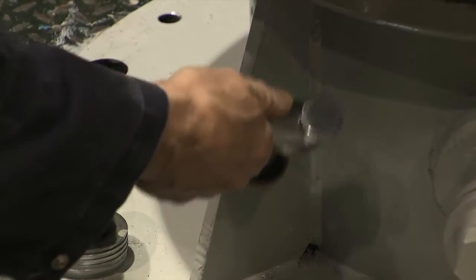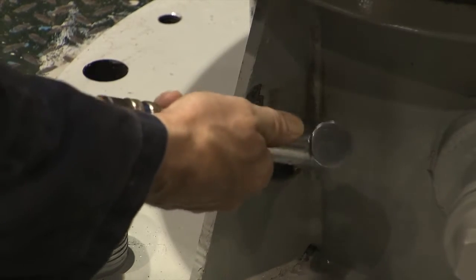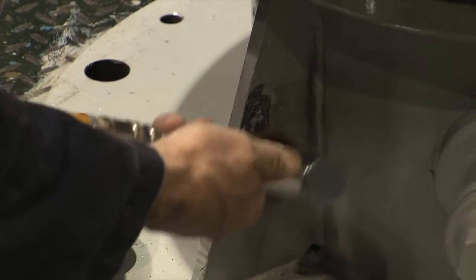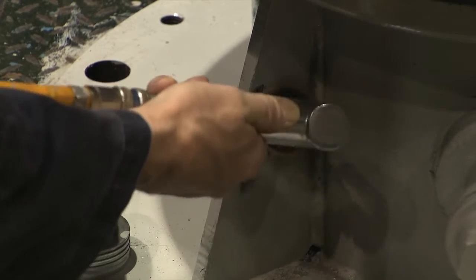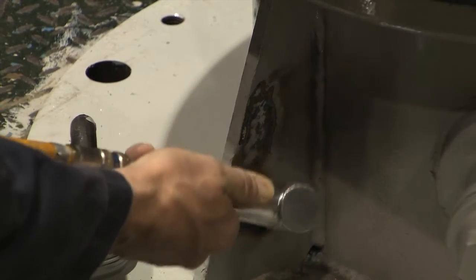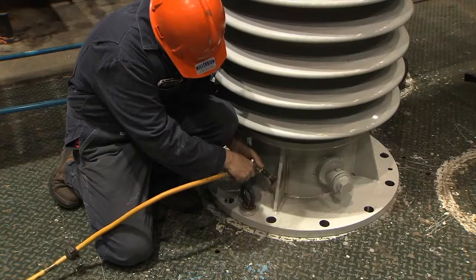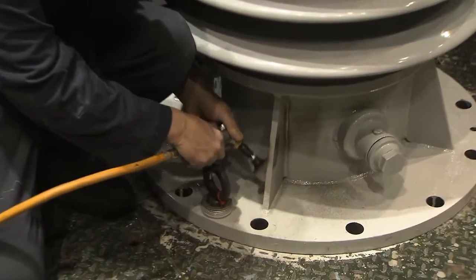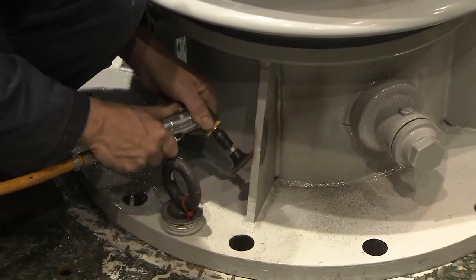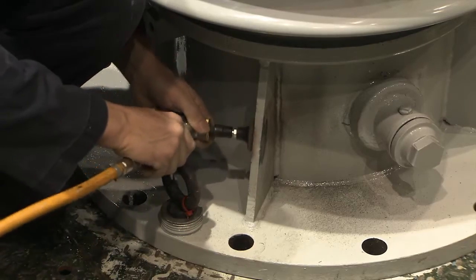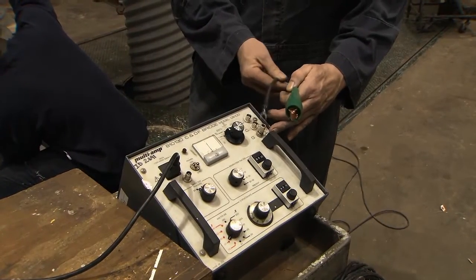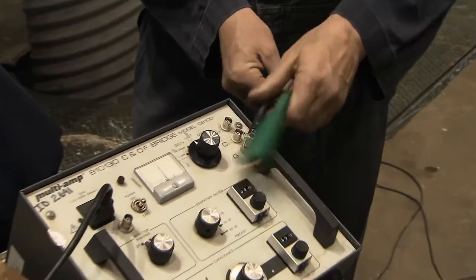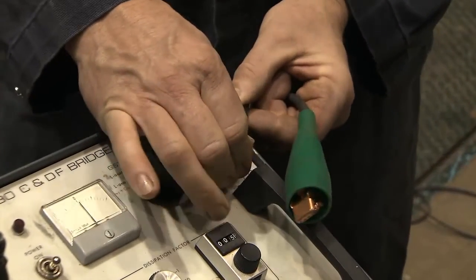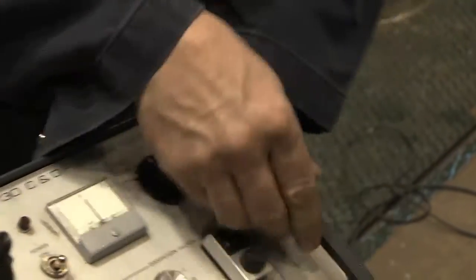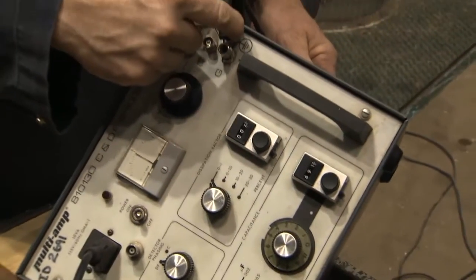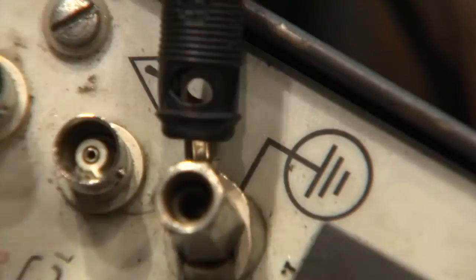Ensure bare metal is achieved by removing a small section of paint from the flange using a pneumatic drill with the appropriate attachment. Grind the paint off a section of the flange that extends from the base to the top of the crown, and grind both sides so that the connector on the cable lead can be clipped to bare metal. The capacitance and dissipation factor bridge used for Doble testing is situated on a dedicated mobile cart that should be stationed approximately 10 feet from the bushing being tested.